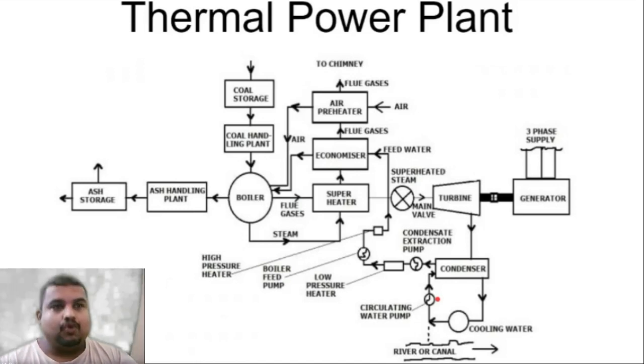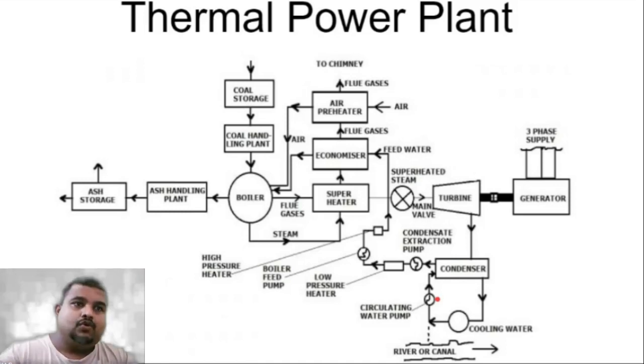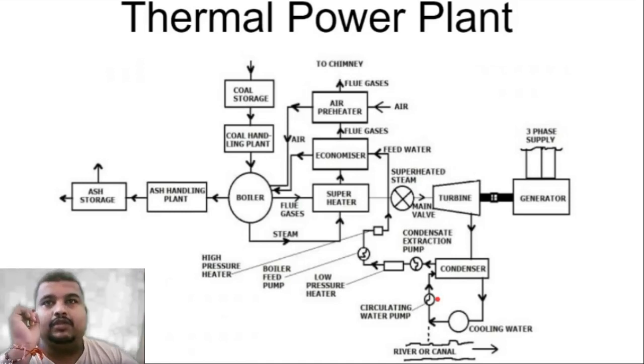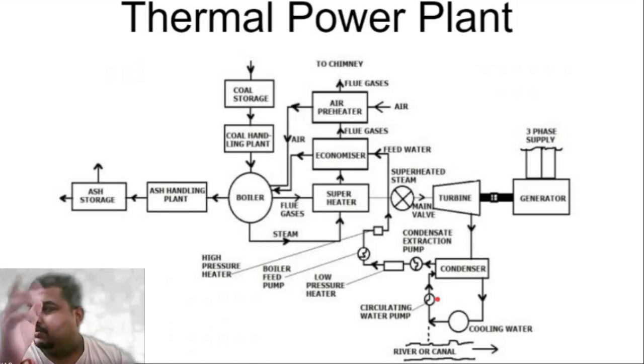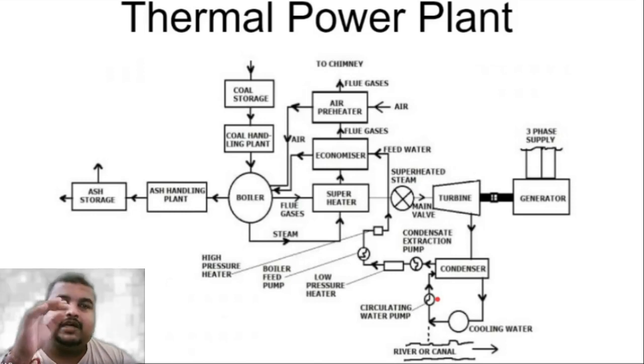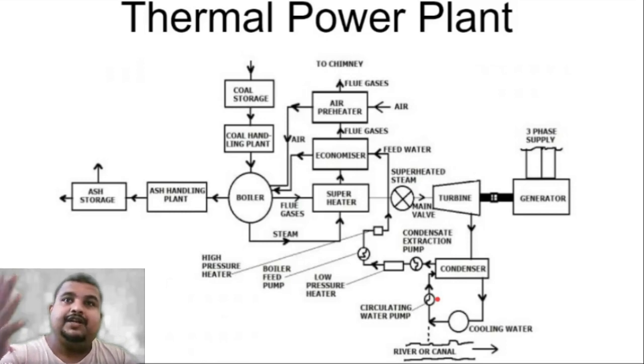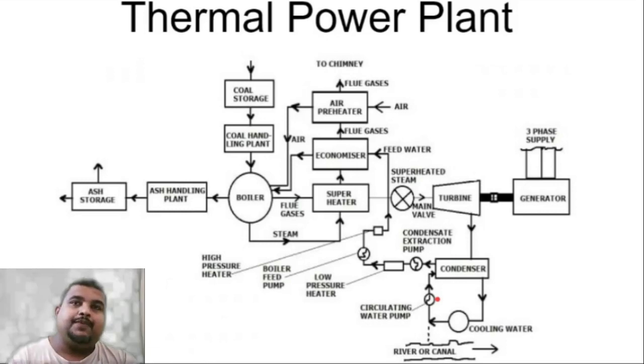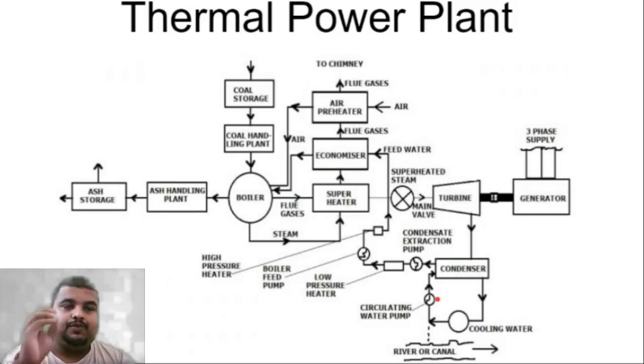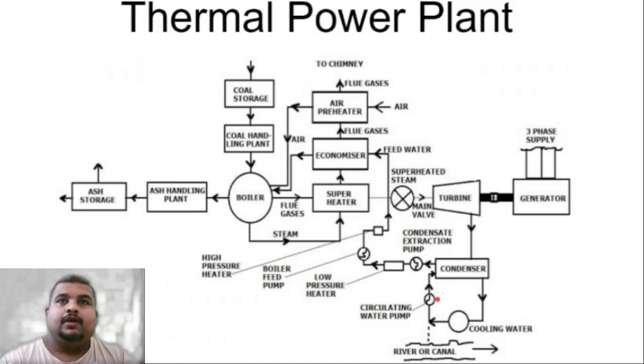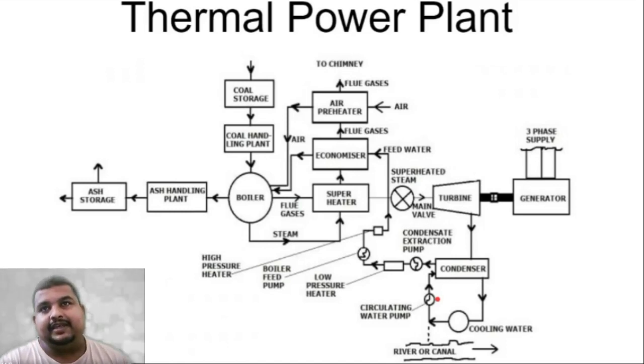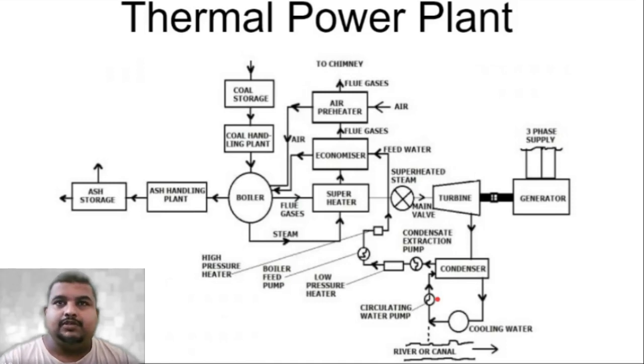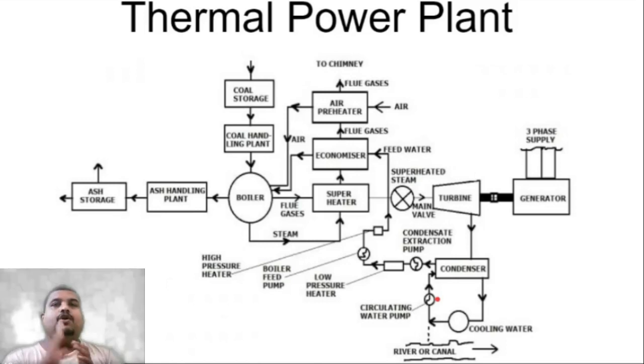Burning coal is not easy. If you think about a normal coal barbecue, it's so difficult that you have to pour kerosene to light it. So imagine in a boiler where 80 to 150 tonnes per hour of coal is burned — the burning rate and burning process will be extremely complicated. We are going to see how coal is provided, how gas and air are provided, and how the ignition system works. First of all, coal has to be stored for a minimum of three months of operation — your coal reservoir must have that much capacity.